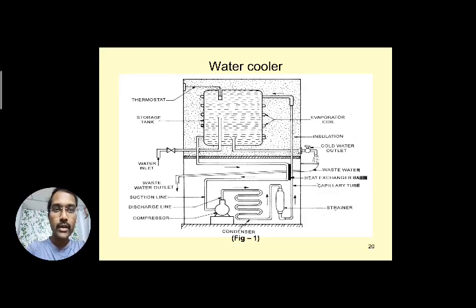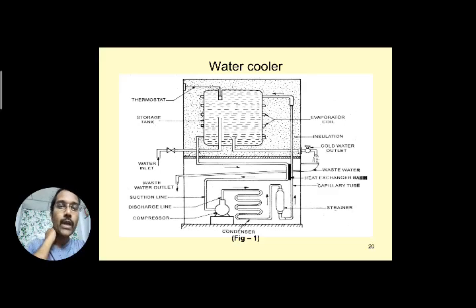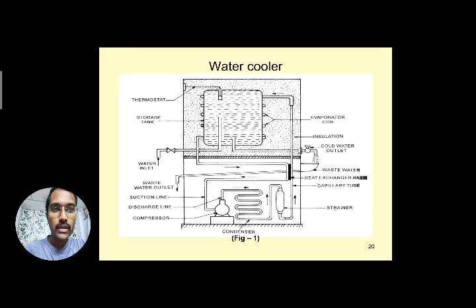Water inlet is usually from the top. From the evaporator tank, the pipeline comes back and where the capillary tube and this return tube meet, heat exchange takes place — acting as a heat exchanger. This pipeline then becomes the suction line connected back to the compressor. So there is a suction line, discharge line, compressor, strainer, condenser, capillary tube, evaporator, thermostat, and a drain pipe for waste water collected in a basin.